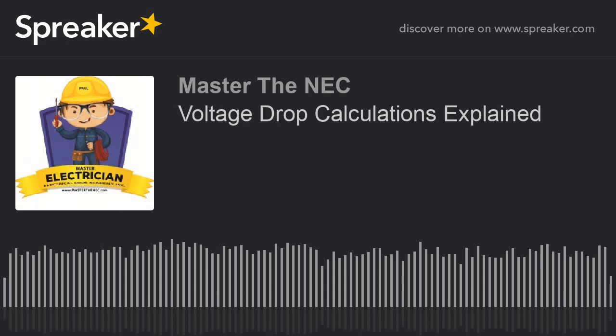All right, so let's take what we've got. Now, let's just assume here that we're dealing at the 120. So let's do some length here. So circular mil, let's get your calculator out. Take 26,240, and we're going to multiply that by the voltage drop, the actual voltage value. In this case, if it's a 120 volt, since we're working with 3%, we don't want to exceed that in our example here. Then we would plug in what the actual voltage drop is. And we determined what that was and how we calculated that. We did that earlier. So it's 3.6 volts.